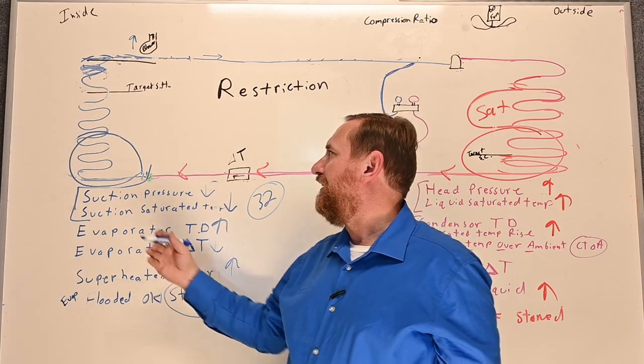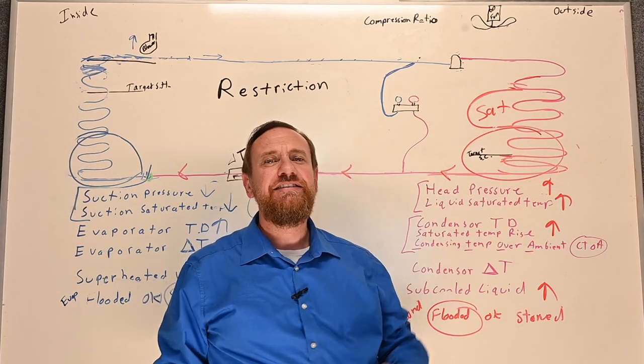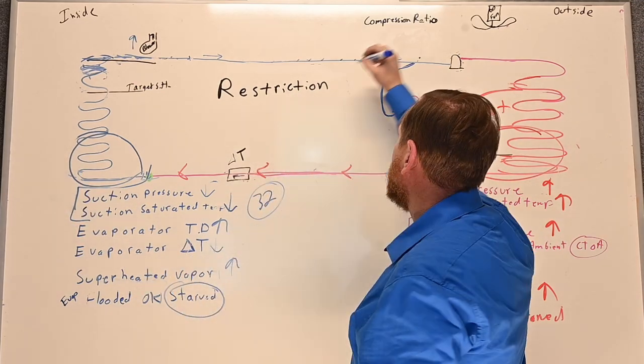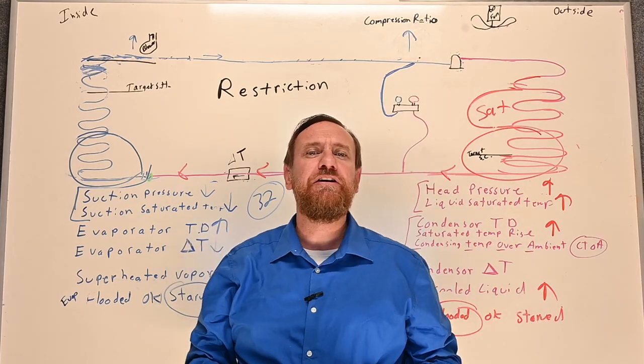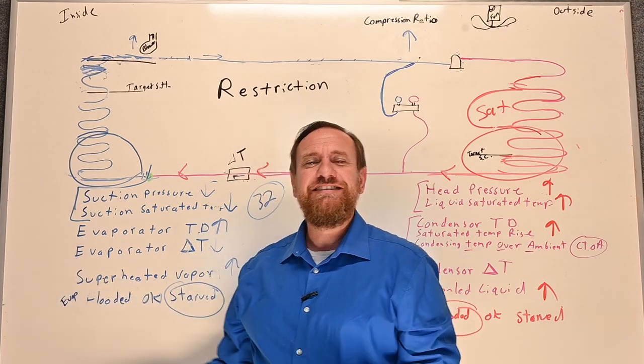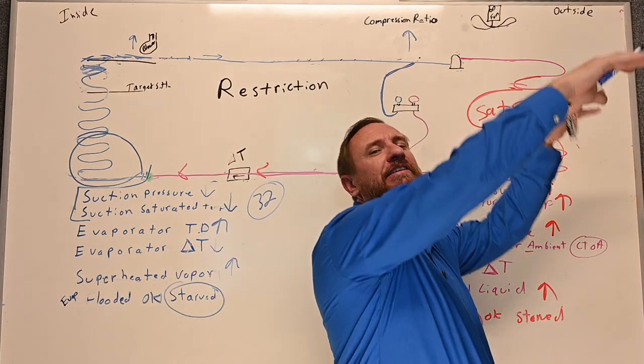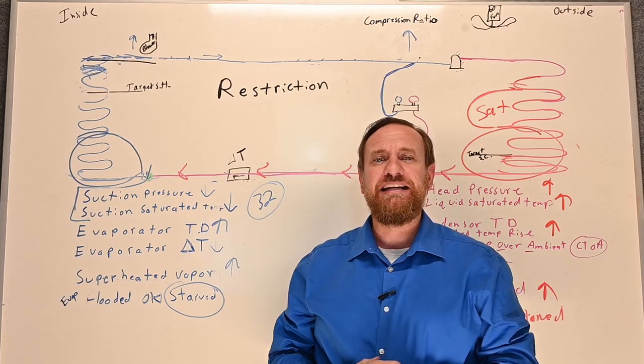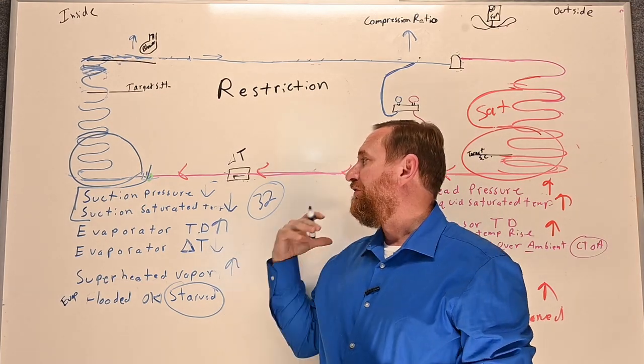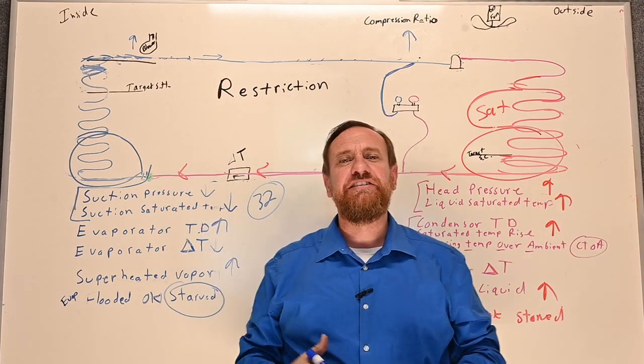Looking at the whole scenario: lower suction pressure and higher condensing pressure means the compression ratio goes up significantly. The compressor now has to pull down to a lower pressure to absorb less dense vapor and then push really hard to build pressure to a higher level. So the compression is doing a whole lot more work. These are the scenarios you're going to see with a refrigerant restriction.